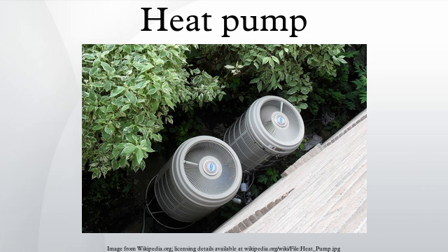Note that an air source heat pump is more efficient in hotter climates than cooler ones, so when the weather is much warmer the unit will perform with a higher COP. Conversely, in extreme cold weather the COP approaches 1. Thus, when there is a wide temperature differential between the hot and cold reservoirs, the COP is lower. On the other hand, ground source heat pumps benefit from the moderated temperature underground, as the ground acts naturally as a store of thermal energy. Their year-round COP is therefore normally in the range of 2.5 to 5.0.